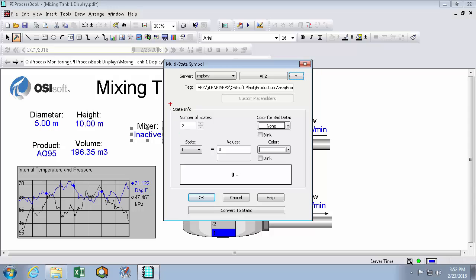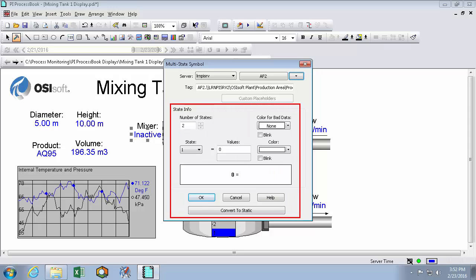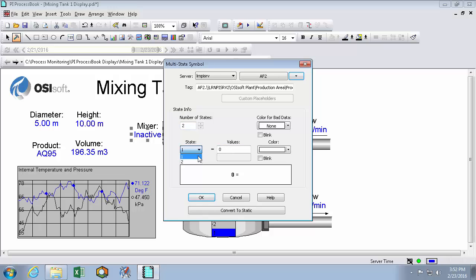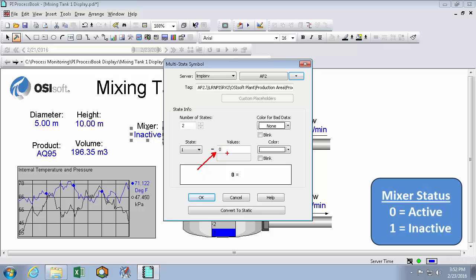And the next thing to do is choose the states. So I want two states. One for active, one for inactive. All multi-state symbols also have another state for when there's bad data. But we'll leave that one blank. The next one we'll choose state 1. So state 1 will take a value of 0. And because my PI point is using a digital state, 0 is mapped to the string active, and 1 is mapped to the string inactive.